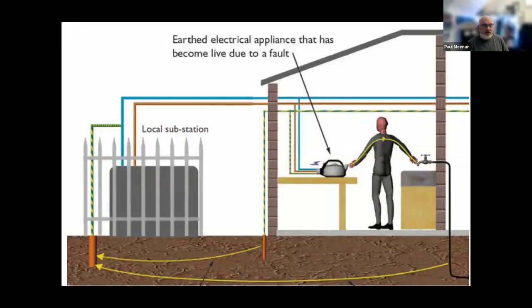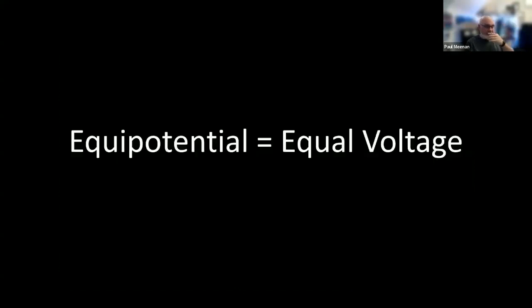So if I bond that water pipe as it enters my building, in theory, I should have an equal voltage. So any fault currents or voltages that connect to any earthed equipment should rise and fall at the same time.